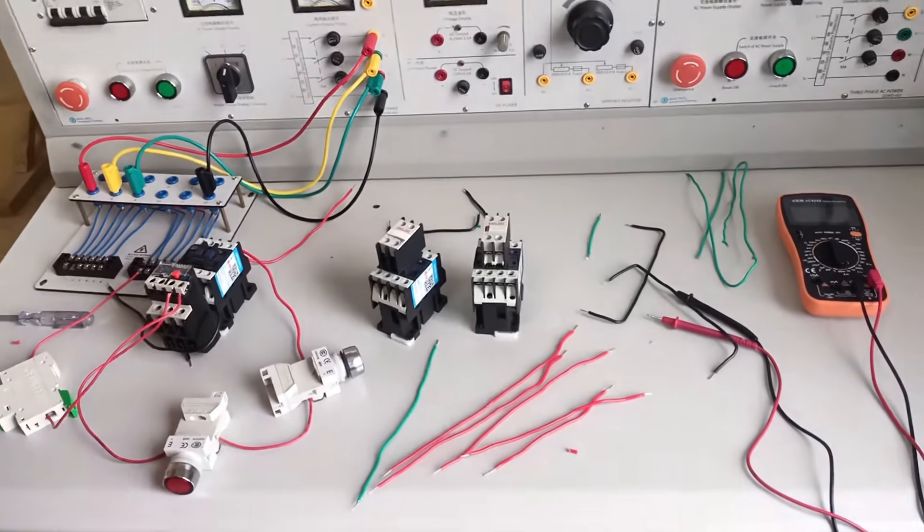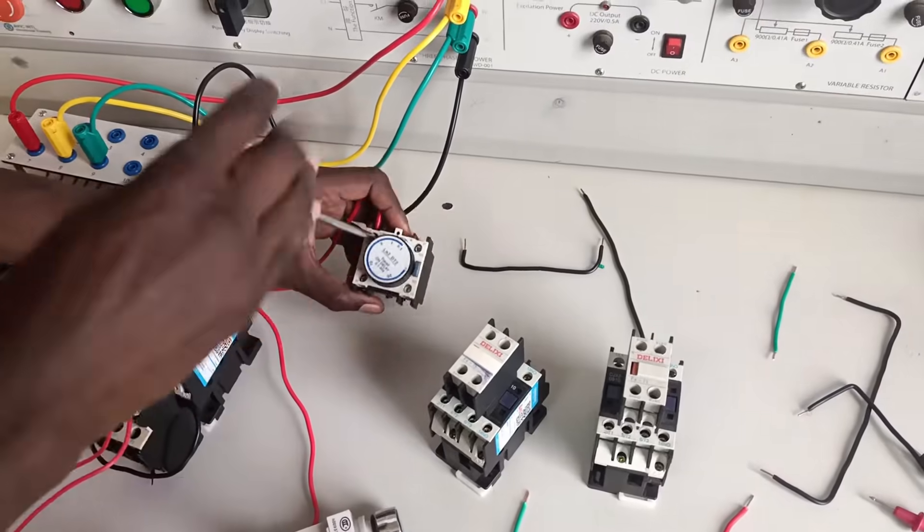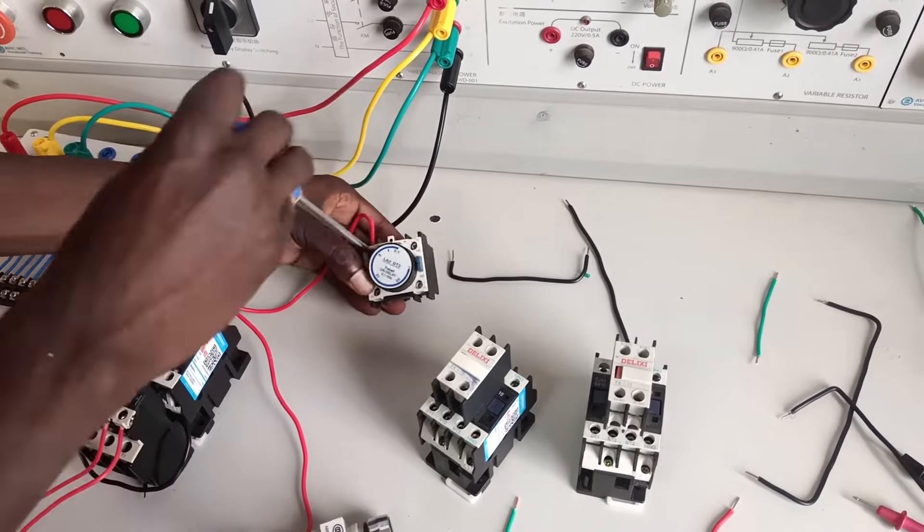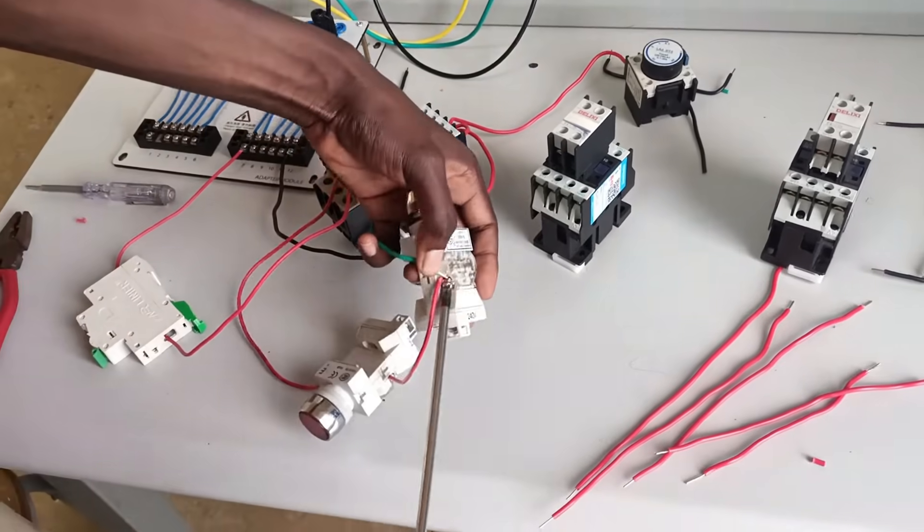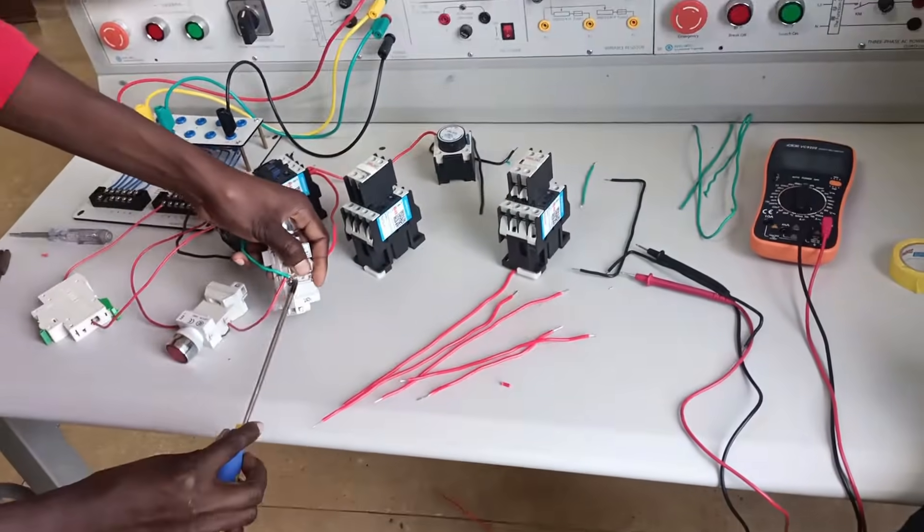Remember we have three cables emanating from A1 of the main contactor, so the timer will take one cable and that cable will go to pin 55. I'm using a manual mechanical delay timer. Let's first connect the holding cable from pin 14 back to pin 3 of the start button. Then let's do the test.